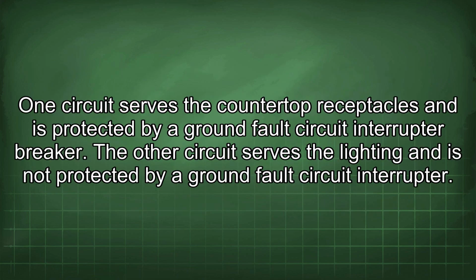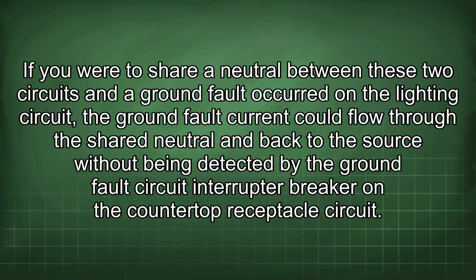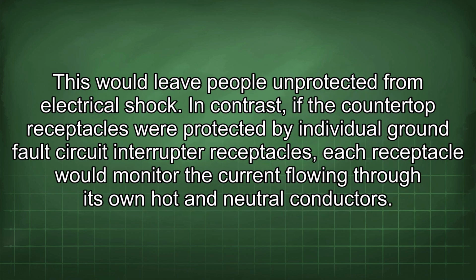One circuit serves the countertop receptacles and is protected by a ground fault circuit interrupter breaker. The other circuit serves the lighting and is not protected by a ground fault circuit interrupter. If you were to share a neutral between these two circuits and a ground fault occurred on the lighting circuit, the ground fault current could flow through the shared neutral and back to the source without being detected by the ground fault circuit interrupter breaker on the countertop receptacle circuit. This would leave people unprotected from electrical shock.